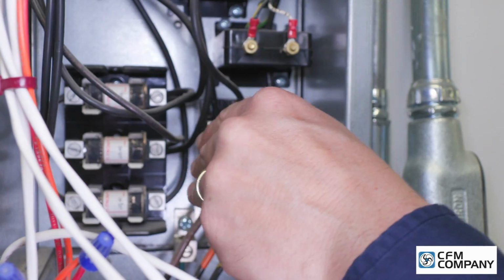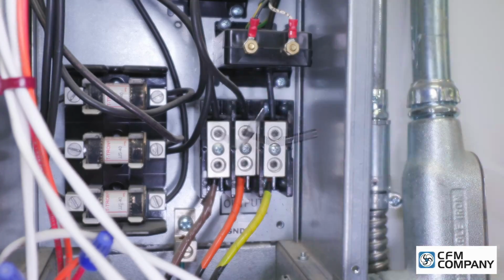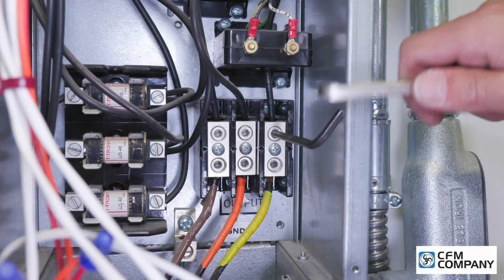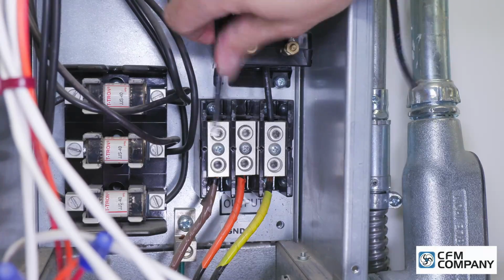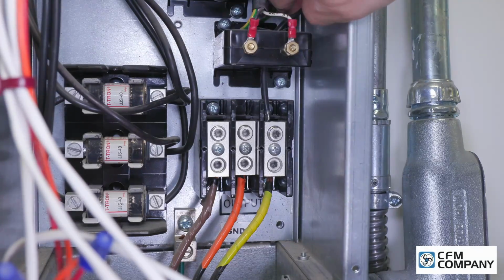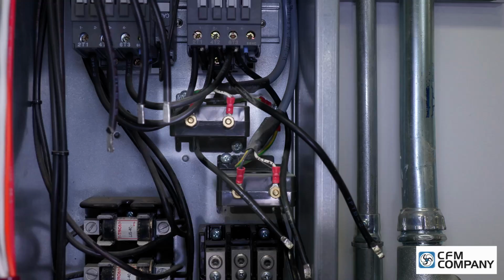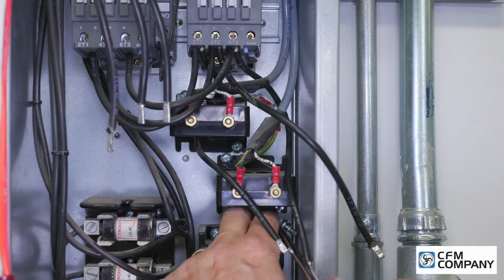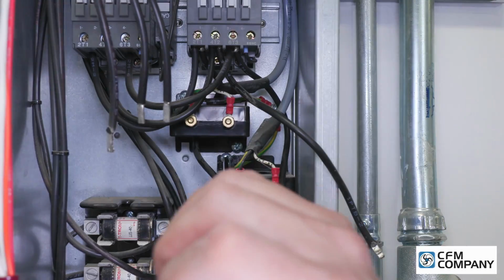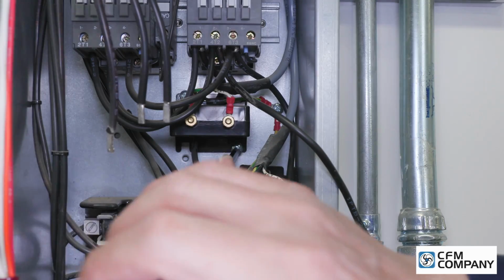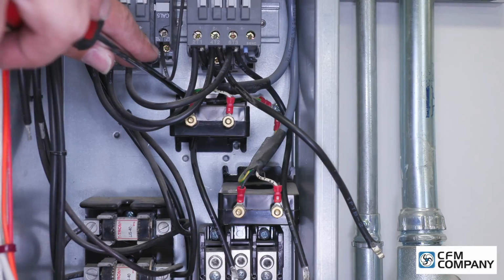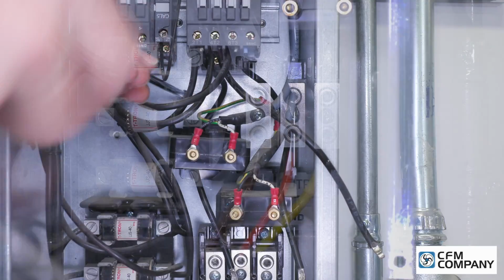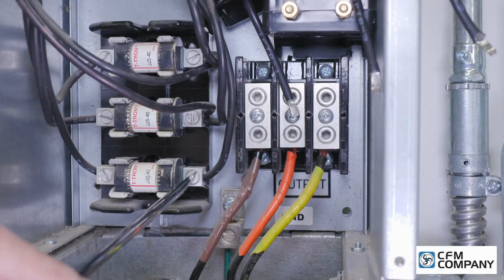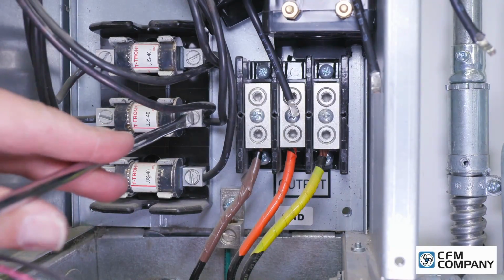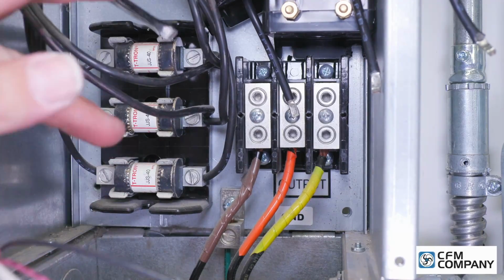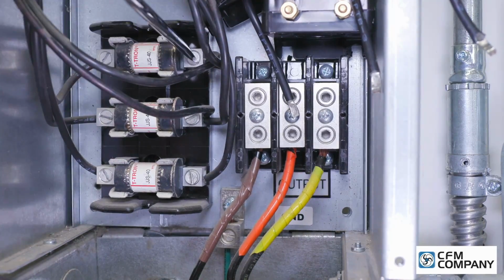Next, remove the line side wires from the motor terminal block. Keep the three-phase motor leads connected. Remove the two current transducers from the back plate. Remove the line side wires from the fuse block. The three-phase wires that connect to the VFD input terminals will stay connected to the fuse block.